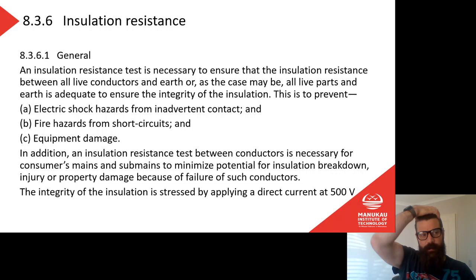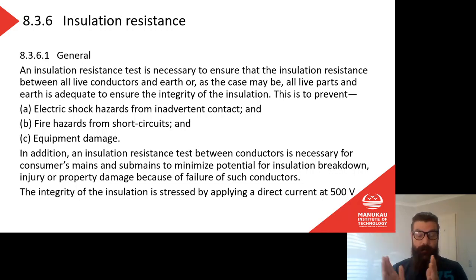The idea there is if the insulation is good against 500 volts, then it's definitely going to be good against 230 volts. And again, when we're talking about stressing insulation, if we go back to our example of water in a pipe, the insulation, in this case, is the pipe itself. So insulation breakdown or faults in the insulation or anything like that is the equivalent of a leak in that pipe. If I've got a hole in my pipe, the water's going to come out.